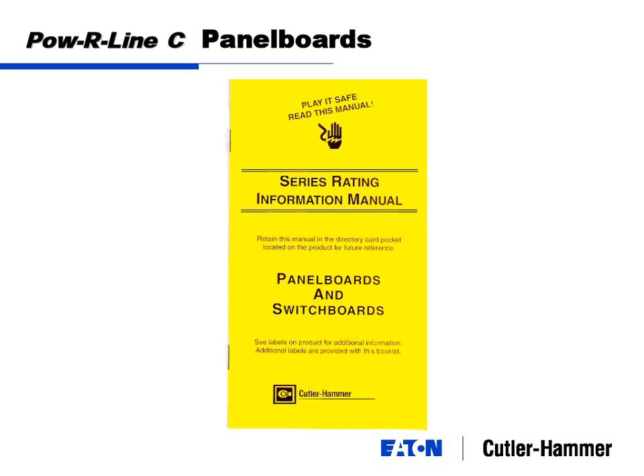these two breakers can be actually both rated 65K or 10K, depending on what panel it goes in, and you know, obviously the catalog number is different, but they will both look similar. So he may look at it and say, hey, I can just put in one of these. I got one in my truck. And that's the concern, that, you know, it is susceptible to a misapplication if not properly followed. And that's why labeling and the series rating booklet in each of the series rated panels is, well, required by UL and mandated.